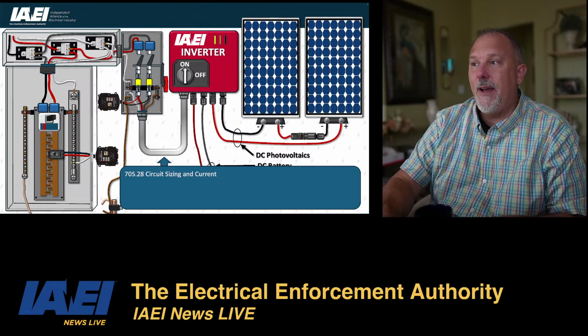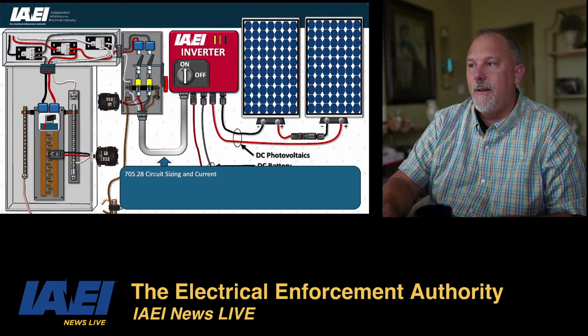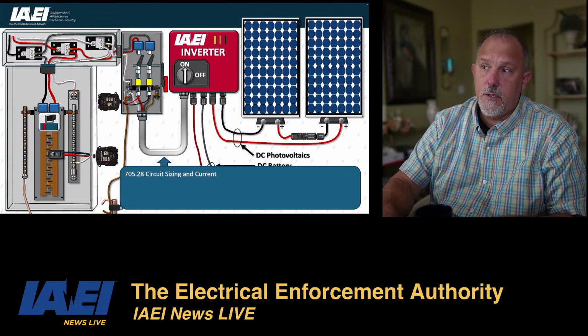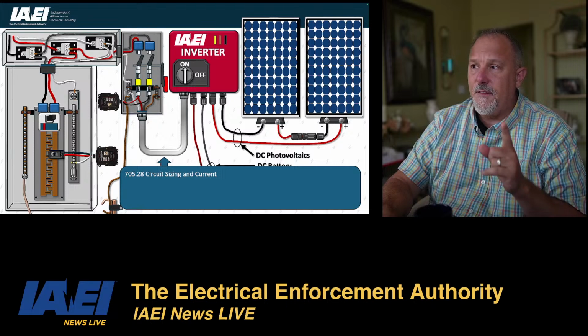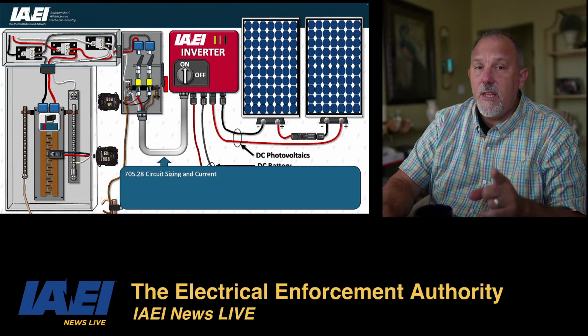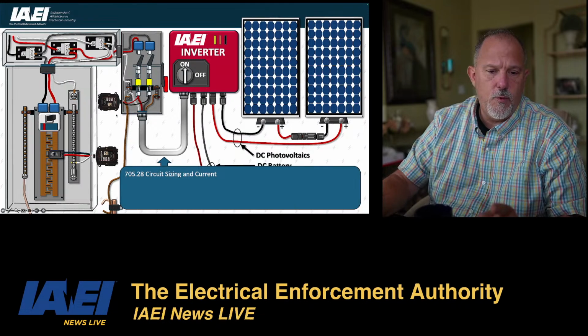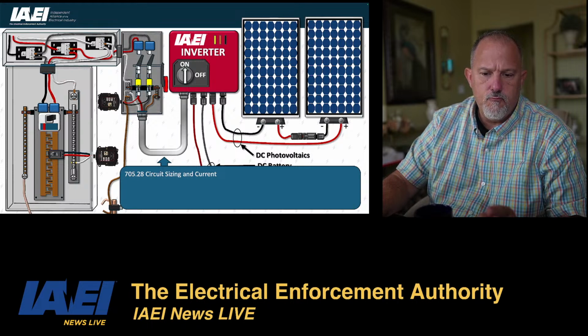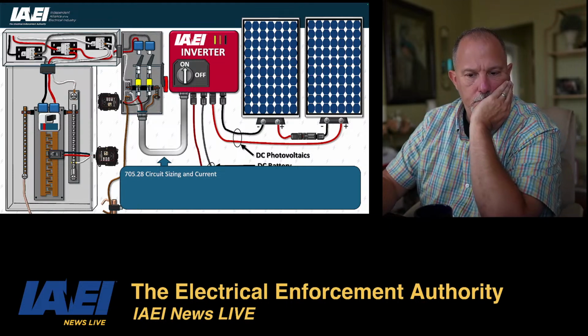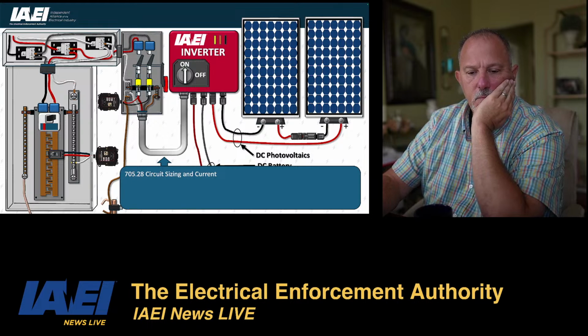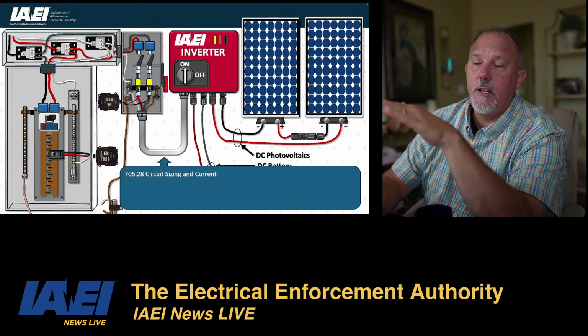The other issue that you have with that disconnect is that the load side of those fuses are not barriered. Now, if this is a utility interactive inverter, let's take a look at 705.11. 705.11 doesn't say utility interactive inverters. I need to add that clarity, because here's where I'm going.